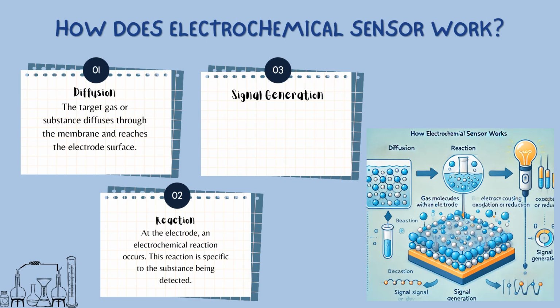The third and final step is signal generation. The electrons produced during the reaction flow through the circuits inside the sensor. This flow of electrons creates an electrical current. The amount of current generated depends on how much of the target gas is present. Higher concentrations produce more current, while lower concentrations produce less. This relationship allows the sensor to measure the concentration of the gas.